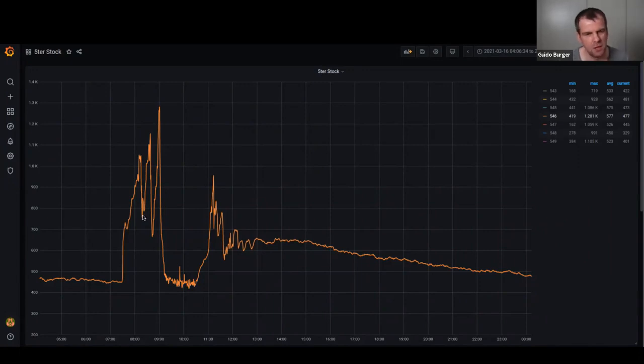It's 750 something. Closing the window, and you see how quickly this value is catching up again and is traveling above 1,100, close to 1,200. Again, he gets a warning, and he's opening the window again. Not long enough, closing the window. And again, you see how quickly the value is going up. What you're noticing is that every time, the aerosol density as well as the CO2 level in the classroom keeps growing. We are not really efficiently ventilating the room, even though he opened the window twice.